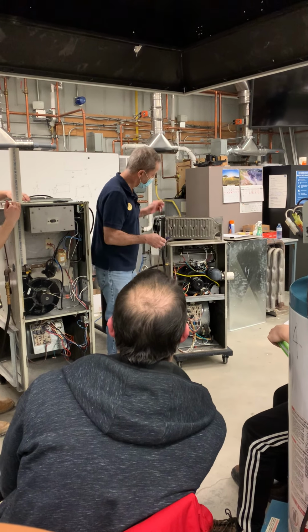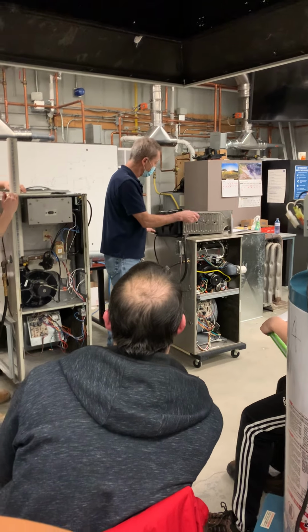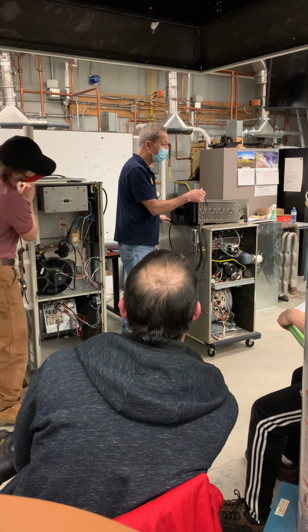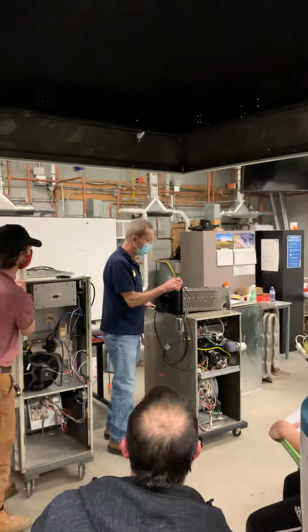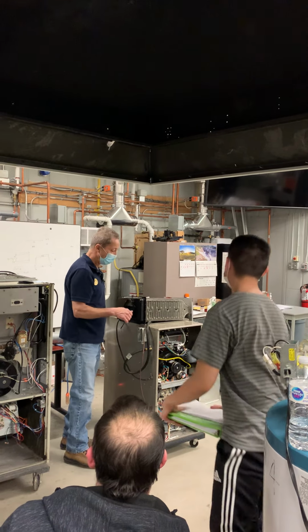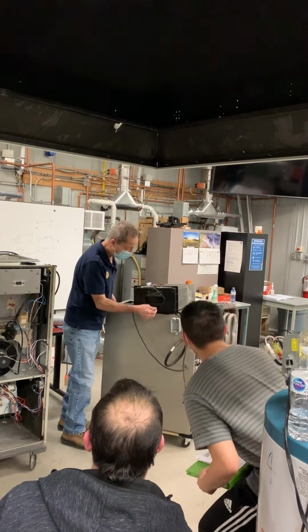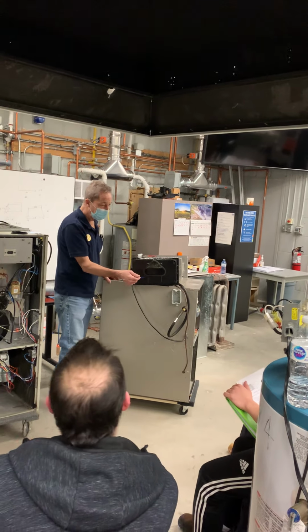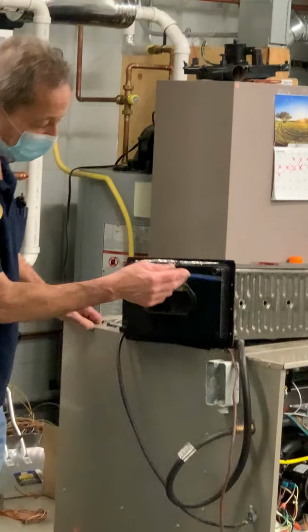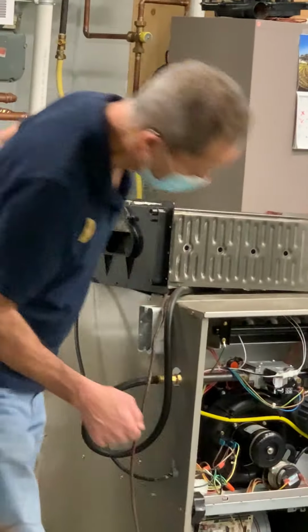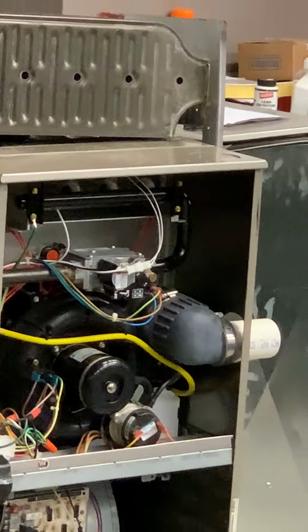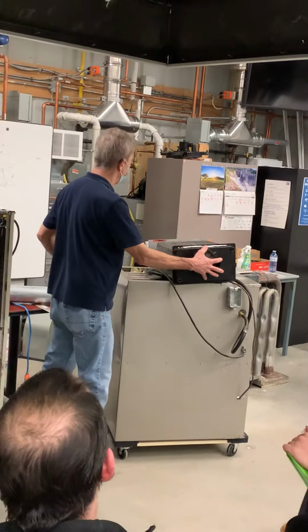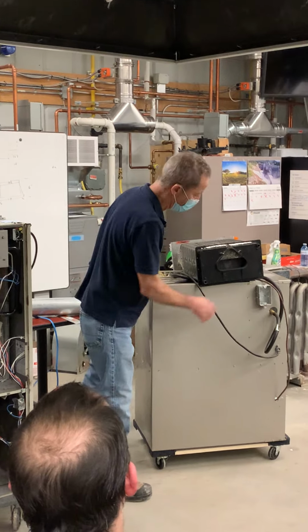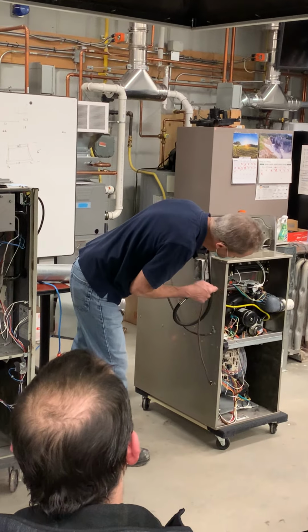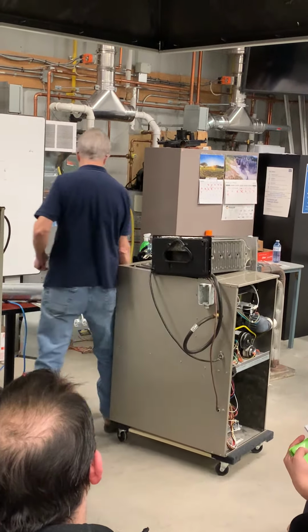So let me tell you something. This item right here is a heat exchanger of a similar furnace. This is the secondary heat exchanger. So what happens is, this side right here is where the inducer fits. If you look at this black plastic section, and this one over here, there's the black plastic section. The inducer motor sits right on here and it sucks. Okay? And while it's sucking, it blows the exhaust out. So let me show you this.